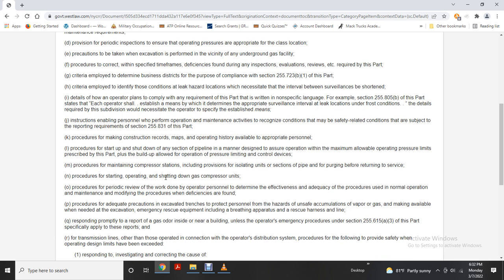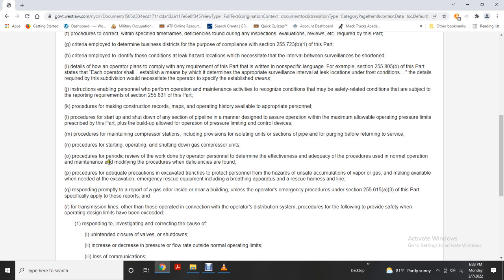K, making construction records, maps, and operating history available to appropriate personnel. Procedures for startup and shutdown of any section of the pipeline in a manner designed to assure operation within the maximum operating pressure limited by this part, plus buildup allowed for operation of pressure limiting and control devices. Procedures for maintaining compressor stations, including provisions for isolating units and sections of piping and purging before returning to service. Procedures for starting, operating, and shutting down gas compressor units. A procedure for periodic review of work done by operator personnel to determine the effectiveness and adequacy of procedures used in normal operation and maintenance, and modifying the procedures when deficiencies are found.